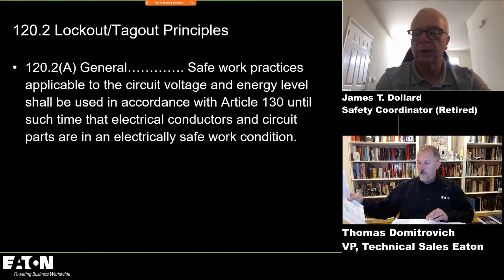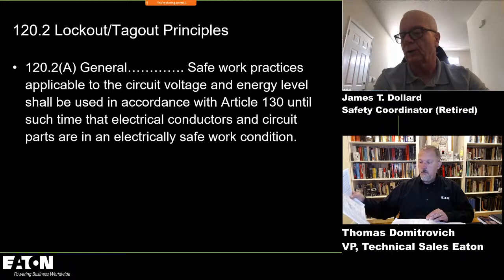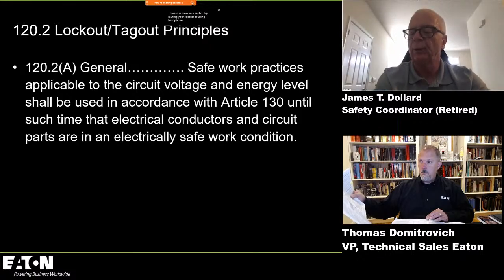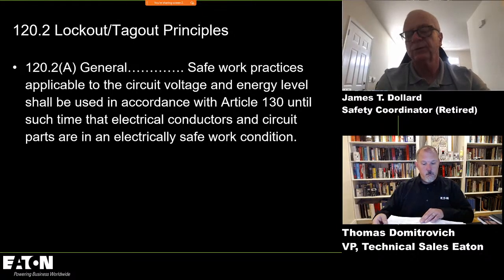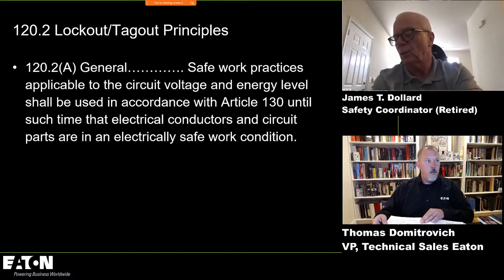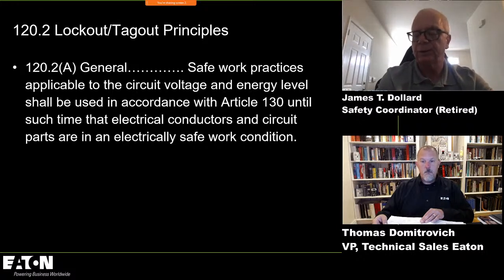So it doesn't matter, if we're going to de-energize and create an electrically safe work condition in a panel board or a switchboard or a motor control center, we need to do a shock risk assessment and an arc flash risk assessment. We need to determine all the PPE we need if we were going into that equipment in an energized state, and we need to be wearing that while we verify absence of voltage. After we verify absence of voltage, and we have established, in accordance with 70E, an electrically safe work condition, and we maintain that state, then we don't need PPE.